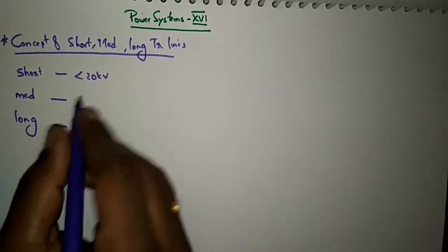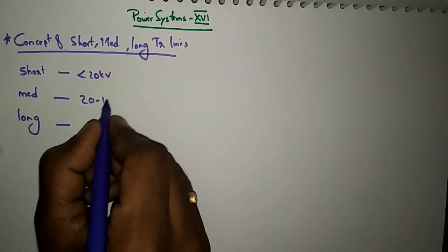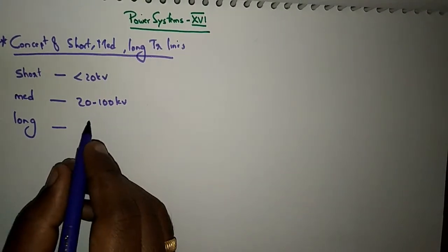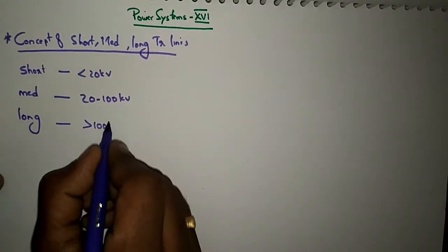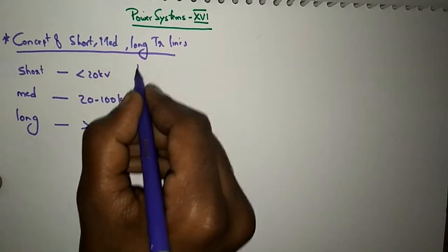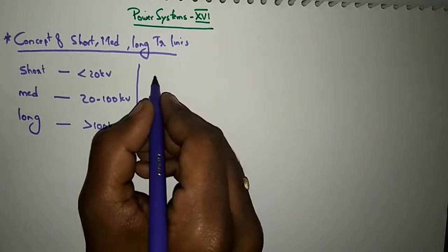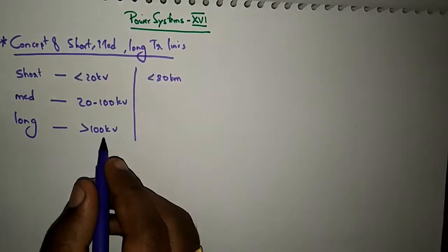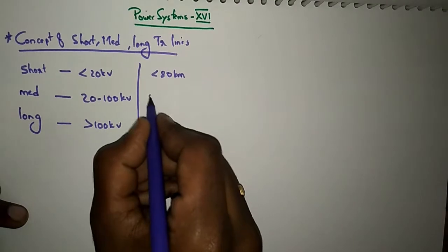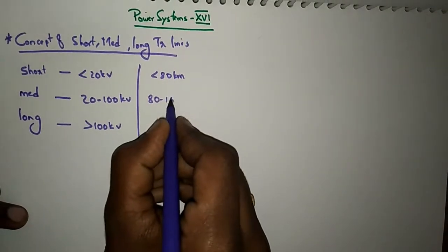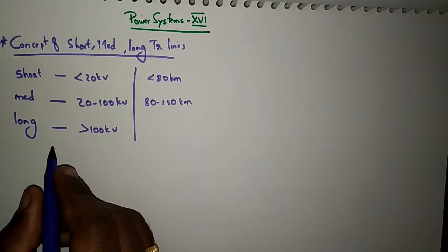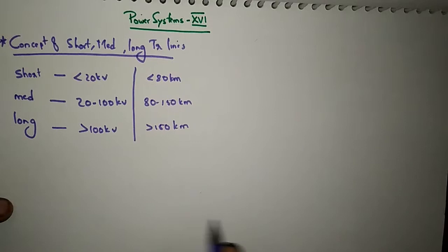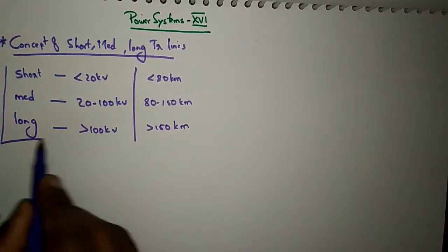If the operating voltage is less than 20 kV, it is a short transmission line. If the transmission voltage is between 20 to 100 kV, it is a medium transmission line. If it is greater than 100 kV, we call it a long transmission line. Similarly, distance thresholds also apply in classifying transmission lines.